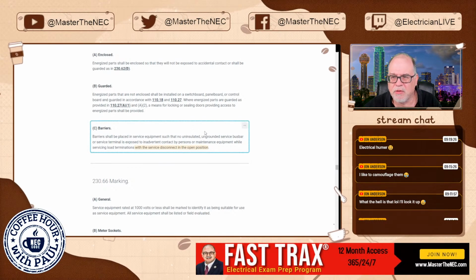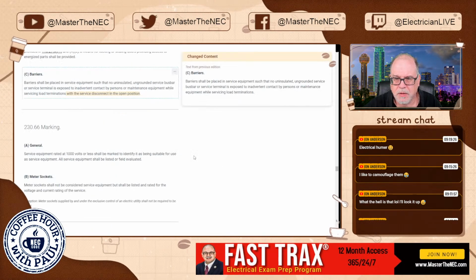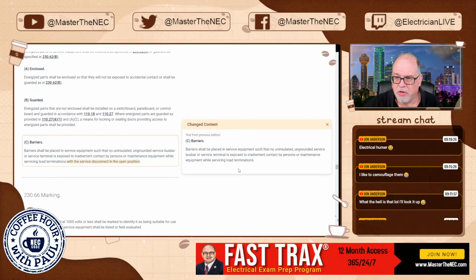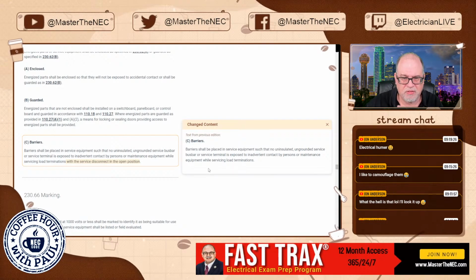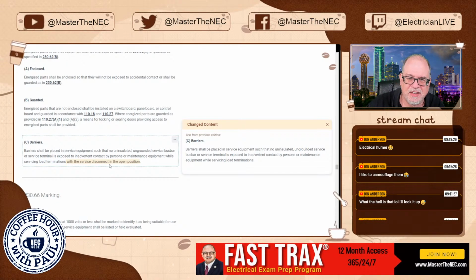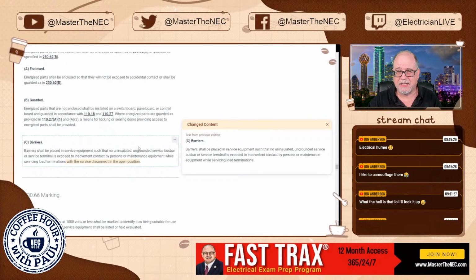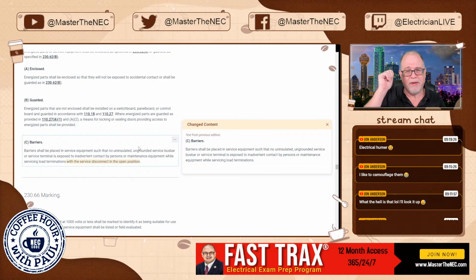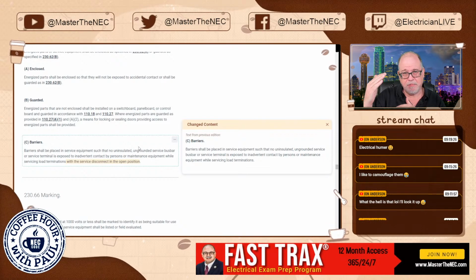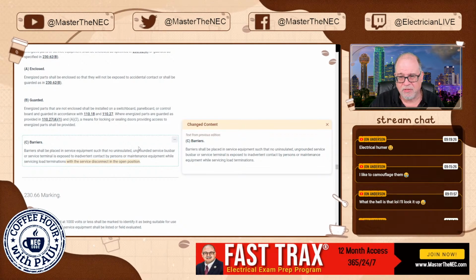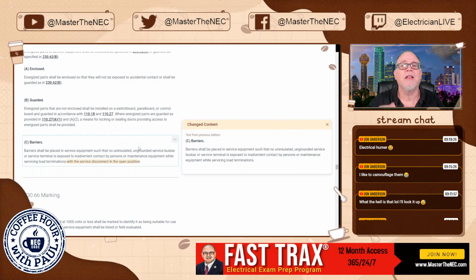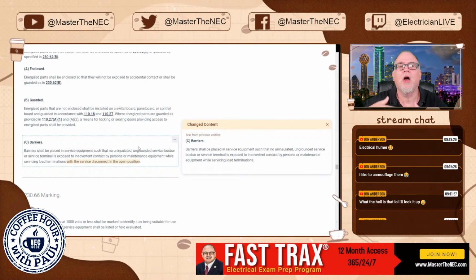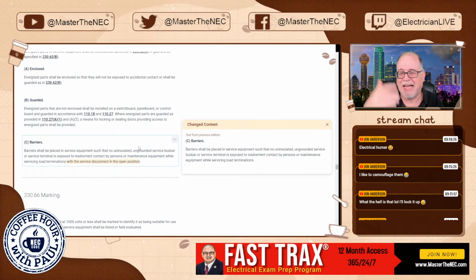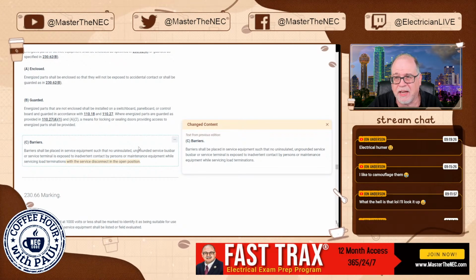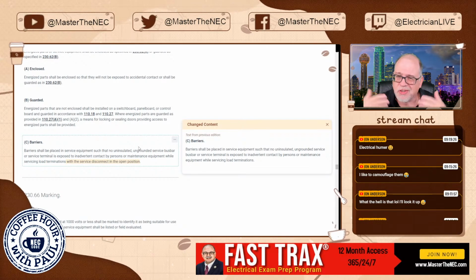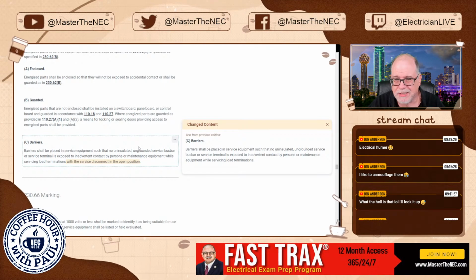Now, the language itself, if we look at the change side by side, you're going to see that everything else is similar. It's just they added this last part because they wanted to make it clear that even if I open the breaker, okay, and so the lower bus is not energized, it doesn't really matter. The bus terminations are still active on the supply side of that service disconnect or that overcurrent protected device. So it's just clarifying it, making it very clear.